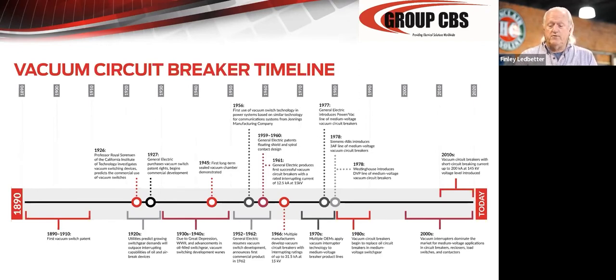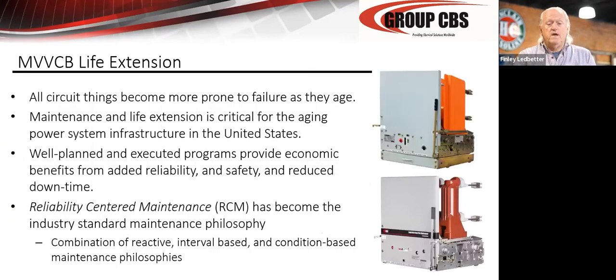This chart, I'm not going to go through it in great detail right now, but certainly review it. If you have any questions, give me a call. You know, all these are prone to aging out. So everything has a bathtub failure curve. Everything from a TV to your vacuum breaker to your automobile to us as humans has a failure curve. You know, if you operate pretty steadily when you're young, if you make it the first few months, you're probably going to make it. If you don't have any infant mortality problems, then you have a long lifetime. And then there is some point where failures begin to come. With the vacuum breaker, that's about 30 years or about 3,000 operations.